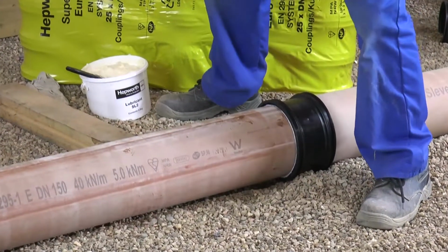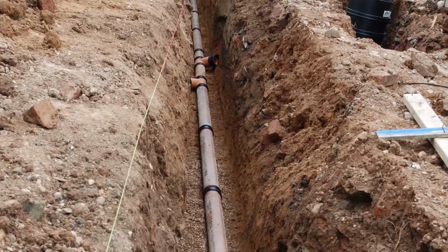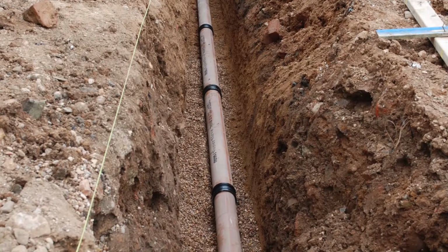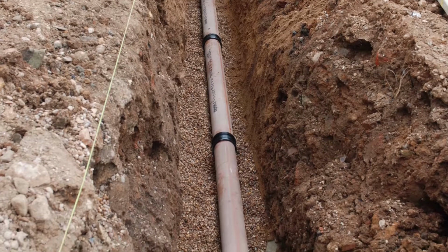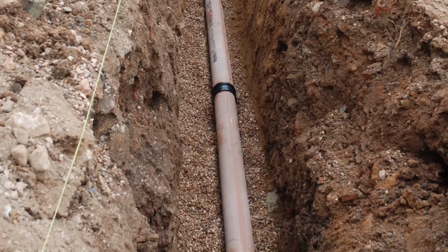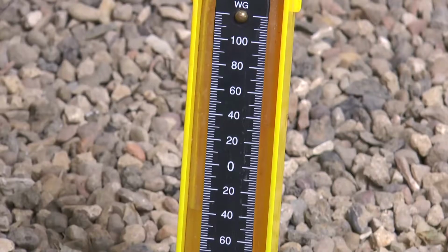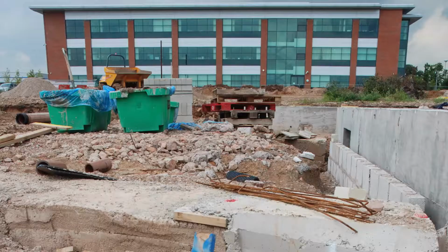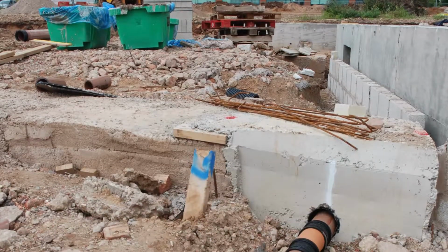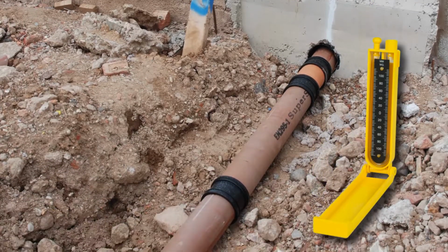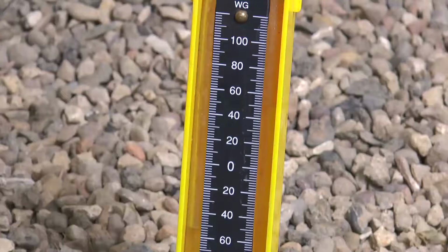After jointing a pipe, be aware that certain external environmental conditions can also affect the test, contributing positively or negatively while the test is underway, contributing to a false result, such as the water or U-gauge level rising. This occurs when the sun shines on the pipeline, increasing the temperature of the air inside the pipe and expanding it as a result, raising the water gauge measurement level.